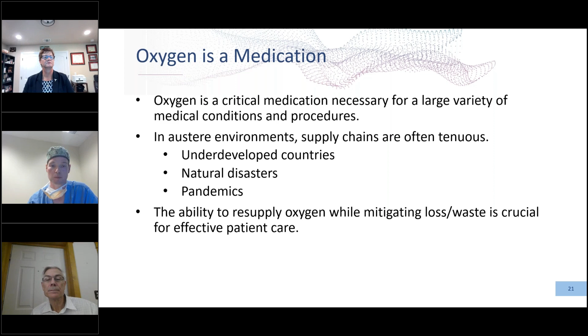So this is an example of something that we're currently using in the field. This is known as a portable oxygen generator, the POGS 33C. I've actually had the pleasure of using this more than once. As mentioned, when I was in Djibouti, I was the oxygen generation officer, and this is actually how I was able to generate the oxygen. This machine is capable of taking ambient air and purifying it to 93% pure oxygen plus or minus 3%, and it can provide that oxygen at flow rates of up to 33 liters a minute at a pressure of 50 psi, which is your standard wall outlet pressure.